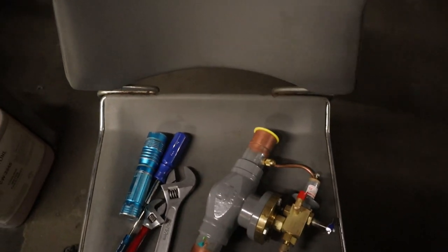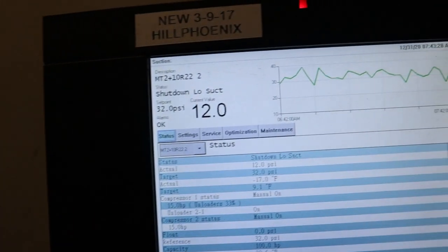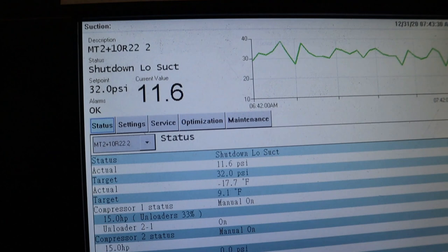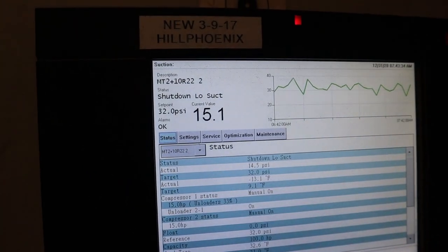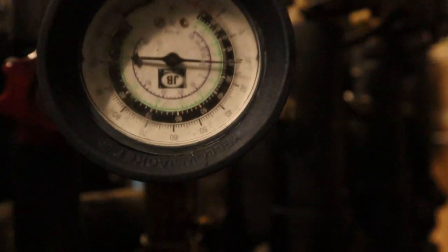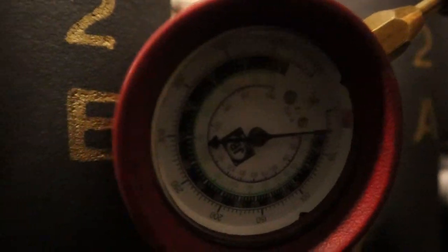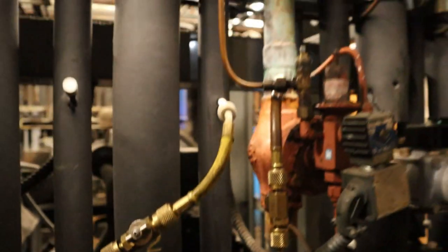If you've seen my previous video on how to pump down a system, you know you have to manually run all the compressors, get as low as you can possible. Right here, 12 pounds, both the manual on, still going down. 22 pounds, both liquid and suction. It's taking a little bit longer, so I'm going to give you one of those Wayne's World dream sequences.